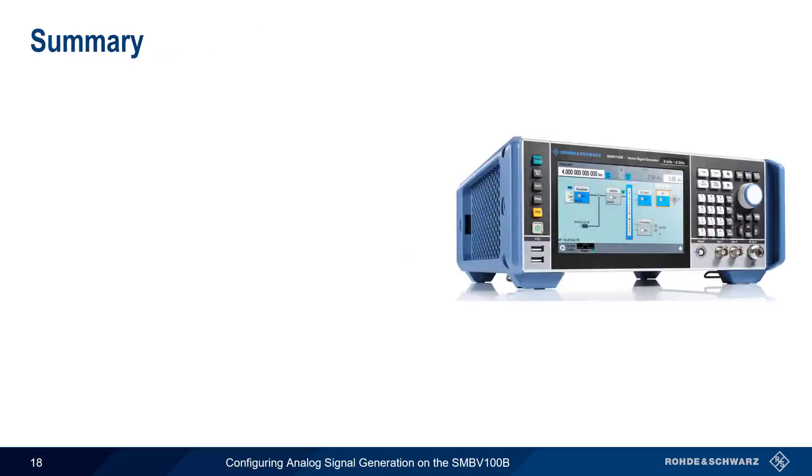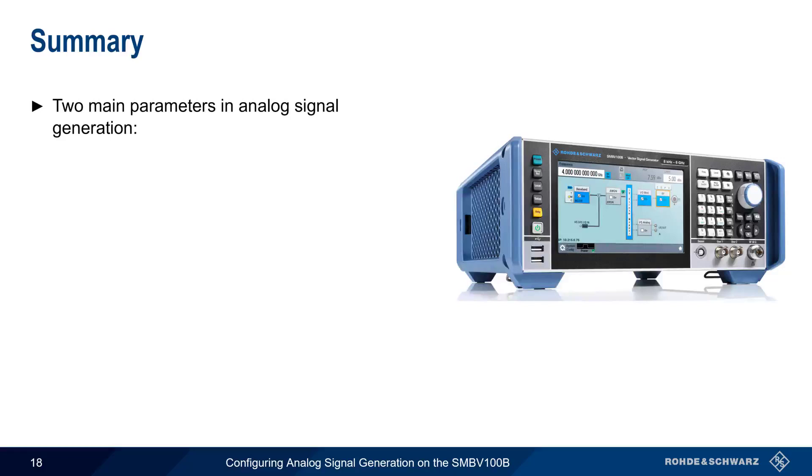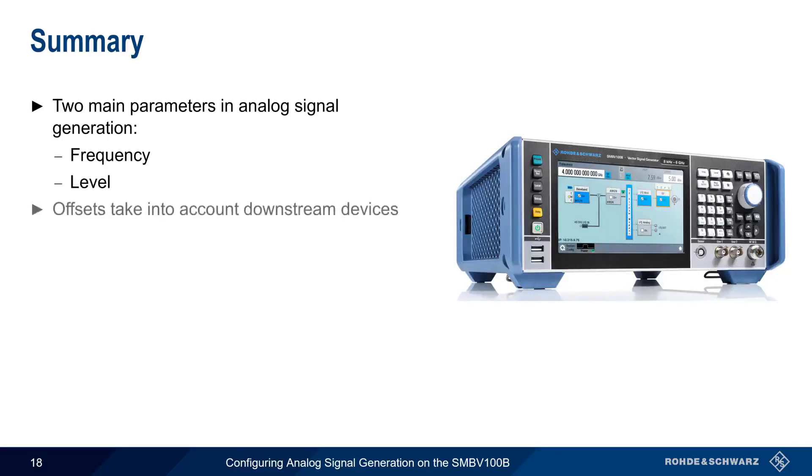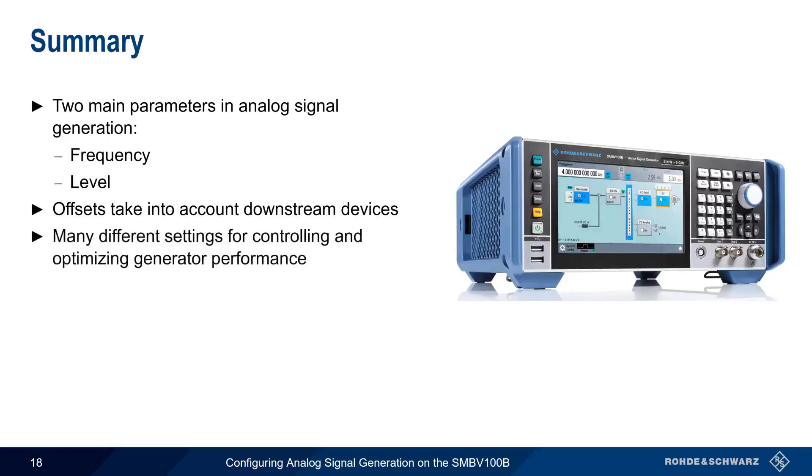Let's summarize what we've covered. The two main parameters in basic analog signal generation are the frequency, which includes the initial phase of the signal, and the level, which on the SMBV also includes a configurable output power limit for safety reasons. We can specify both frequency and level offsets to take into account the behavior of downstream devices, such as mixers, amplifiers, attenuators, etc. There are also many different settings for adjusting or optimizing generator performance. The proper selection and configuration of these parameters is a very advanced topic, but it's good to have a general idea of what these settings are and where they might be useful.